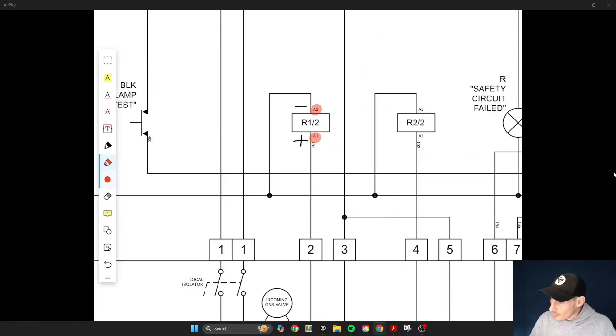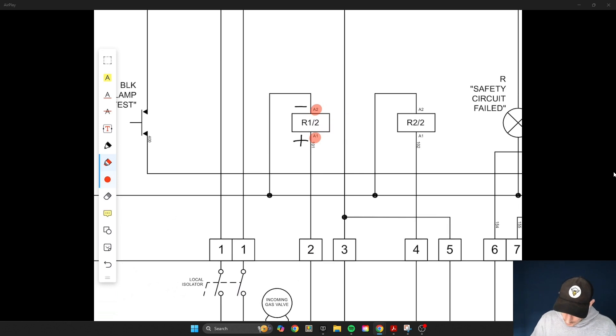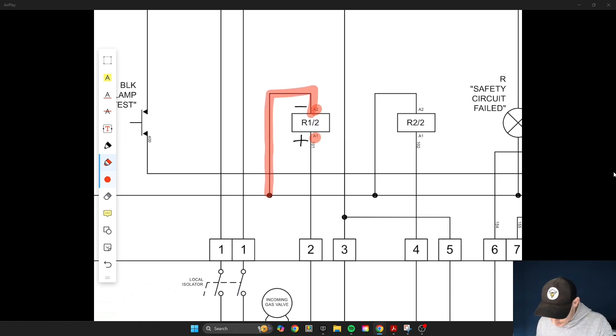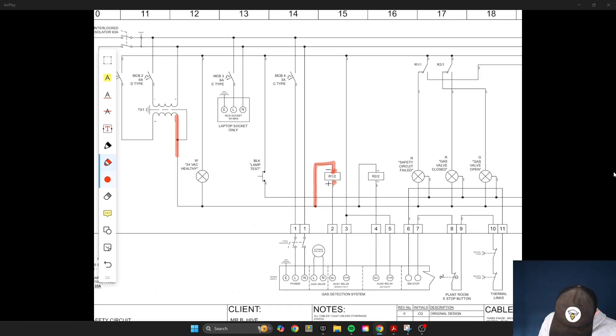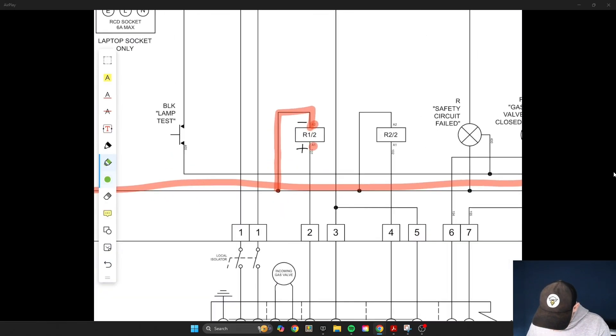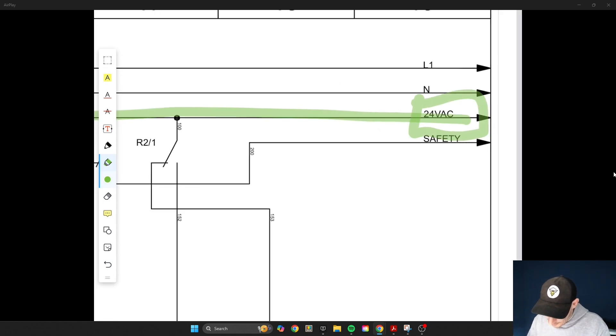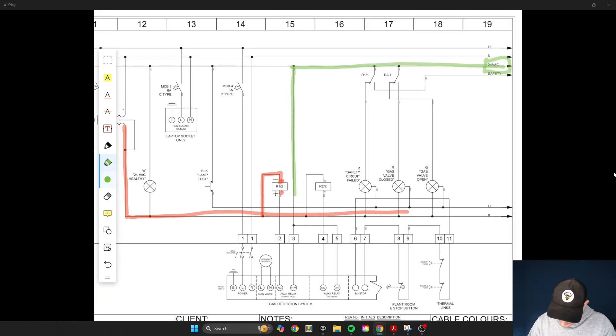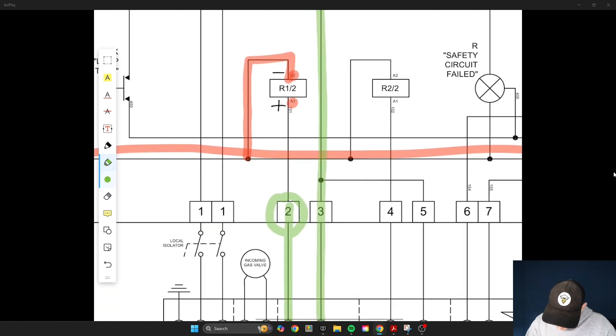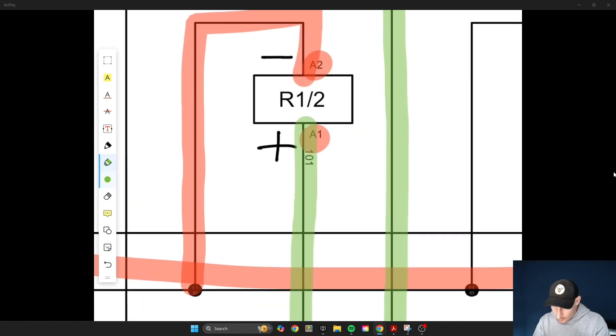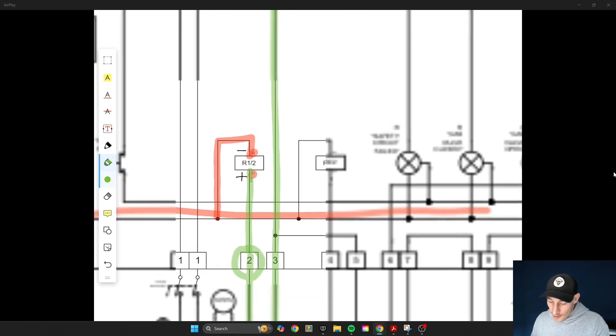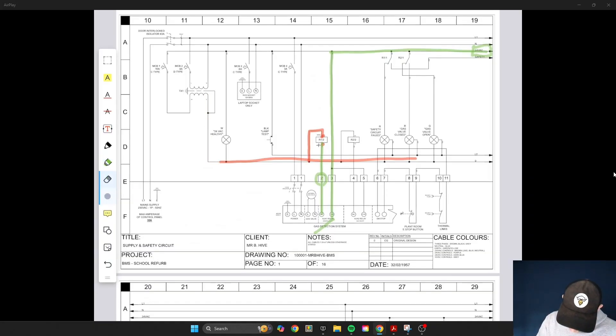To operate that relay — whether it's energized or not — we need a connection to zero volts ground on A2, and you can see here this is coming off the transformer feeding the rest of the drawing. Then we have our 24 volts, and ultimately what happens is it goes through here, something changes out in the field, and then sends it back via terminal block 2, connecting to A1 on the coil side of the relay in the panel.